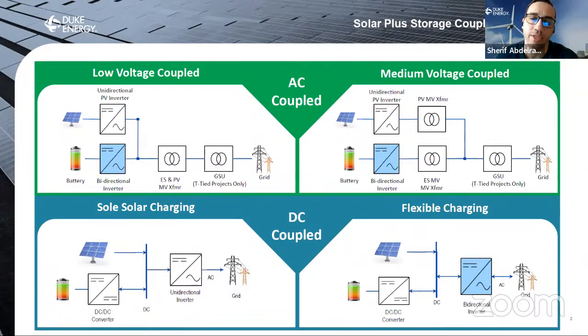So you design the system from the front end to have a bidirectional solar inverter. There are a number of inverter OEMs that offer this feature with just a firmware upgrade, but others simply do not offer it because the hardware within the inverters does not allow for bidirectional operation.